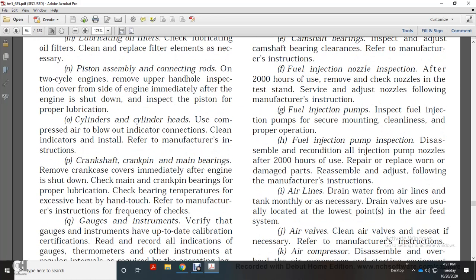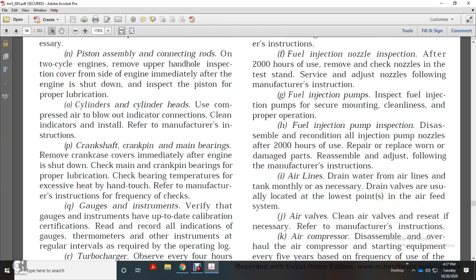Crankshaft, crank pin, and main bearing: check the crankcase cover immediately after the engine shuts down. Check the main crank pin bearing for proper lubrication, and check the bearing temperature for excessive heat with a hand touch. Refer to the manufacturer's instructions for the frequency of the check.